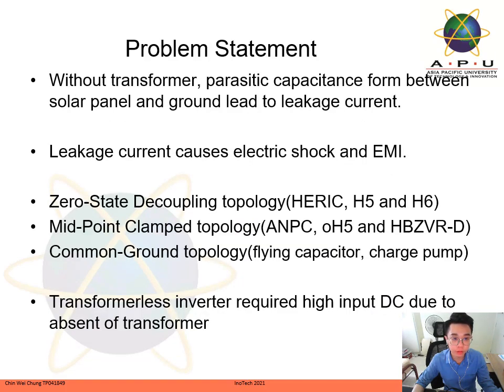In transformerless inverter, without isolation of transformer, a parasitic capacitance will form between solar panel and ground, which leads to leakage current. Leakage current can cause electric shock and electromagnetic interference (EMI). Also, without transformer, the inverter requires high input voltage. To resolve these challenges of transformerless inverter, zero-state decoupling topology was proposed, such as HERIC, H5, and H6 to reduce the leakage current. Then, midpoint clamp topology was also proposed, such as ANPC, OH5, HBZVR-D to eliminate the leakage current, but it requires many components.